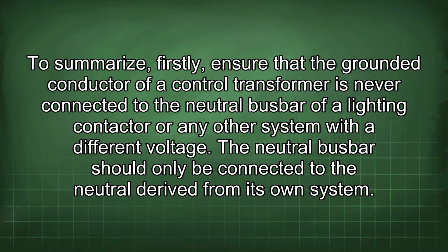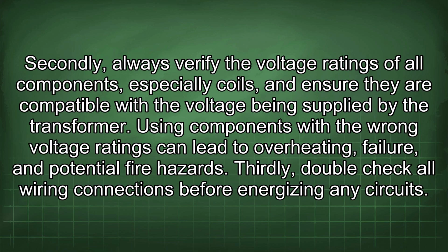To summarize, firstly, ensure that the grounded conductor of a control transformer is never connected to the neutral busbar of a lighting contactor or any other system with a different voltage. The neutral busbar should only be connected to the neutral derived from its own system. Secondly, always verify the voltage ratings of all components, especially coils, and ensure they are compatible with the voltage being supplied by the transformer. Using components with the wrong voltage ratings can lead to overheating, failure, and potential fire hazards.